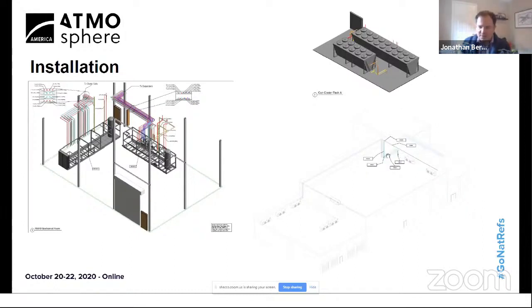Here you can see the piping that was run through the plant connected to the individual evaporators. The low temp brine chill loads aren't shown here, but the piping came off rack B and made its way to those loads. With the CO2 option, the piping is relatively small and each evaporator is piped back to the rack which it serves.